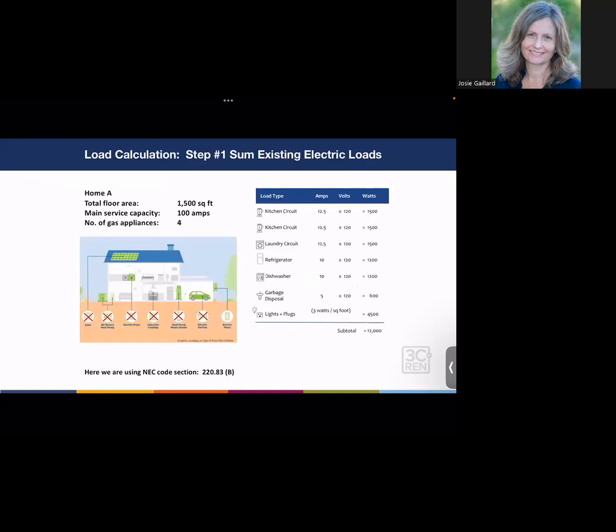Here's our first example. We're taking home A, with some basic assumptions: it's 1,500 square feet, which matters for the electrical load calculation. The main service capacity right now is 100 amps in the service panel. Right now there are 4 gas appliances in the home - I've crossed out the ones they eventually want to convert to electric, but currently they have all 4 gas appliances: furnace, water heater, range, and dryer.